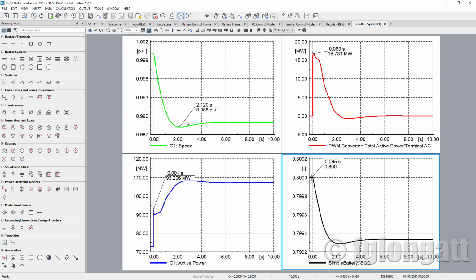What is happening is that in this region, the ROCOF changes polarity or sign. I mean, the ROCOF starts being negative, but then when the frequency starts to recover, the sign of the ROCOF changes, and now the battery is taking energy from the power system.